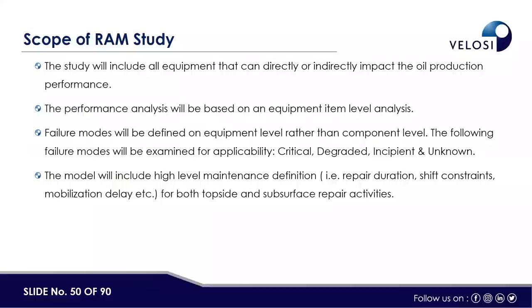The scope of the RAM study included all equipment that can directly or indirectly impact oil production performance. Performance analysis is based on equipment item level; failure modes are defined at equipment level rather than component level. Four failure modes are used: critical failure — 100 percent capacity loss during failure and repair; degraded — 30 percent capacity loss during failure; incipient — lower level than degraded; and unknown. If degraded is not attended, it can become critical. An opportunistic maintenance strategy is used for degraded, incipient, and unknown failures — during a critical repair, these are also repaired simultaneously to save time and cost.